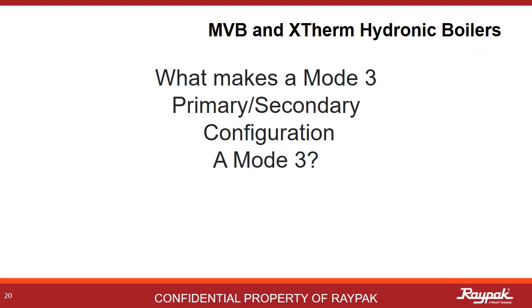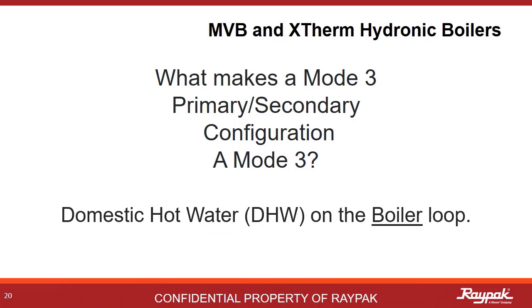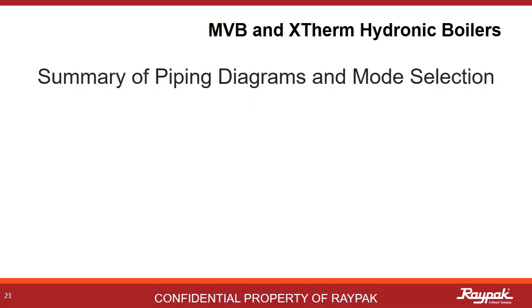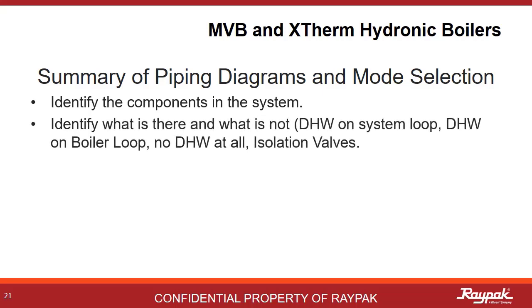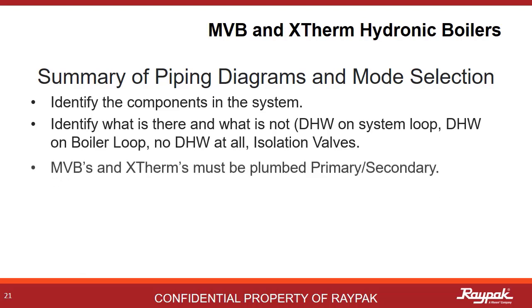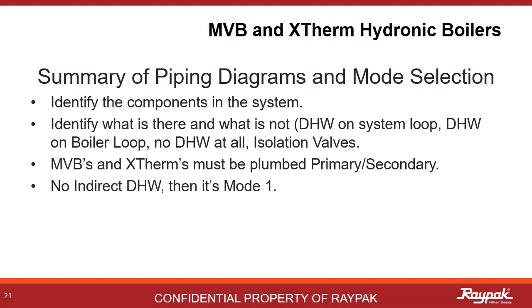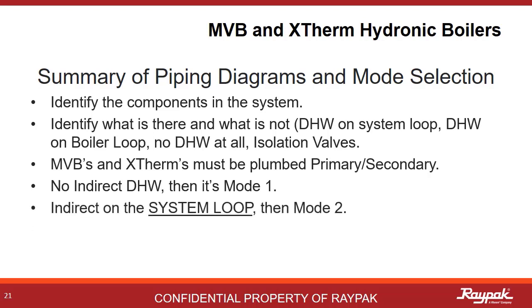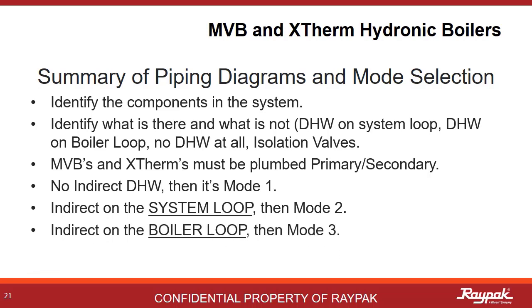So what makes a Mode 3 a Mode 3? It must be plumbed primary-secondary and it must have an indirect domestic hot water system on the boiler loop. Here are some overall pointers on plumbing systems and how they relate to mode selection for type H boilers. Identify all of the parts of the system — look for what is there as well as what is not there. Make sure it is plumbed primary-secondary. In most cases, with no indirect domestic hot water present, Mode 1 will be your choice. If you have an indirect domestic hot water present on the system loop, then it's a Mode 2. If the indirect domestic hot water is present on the boiler loop, then it's a Mode 3.